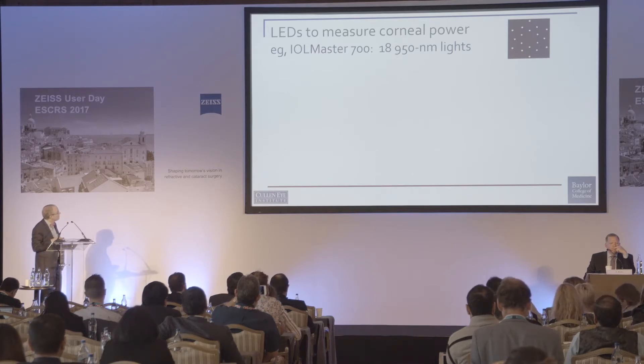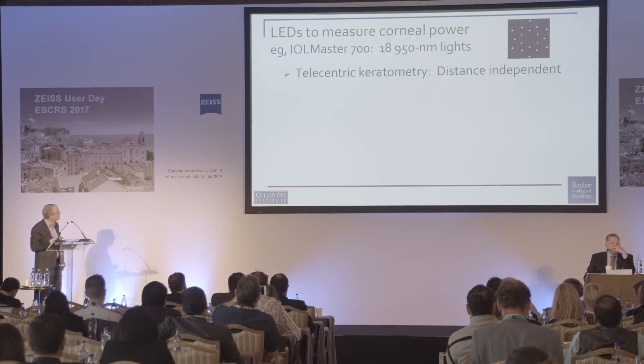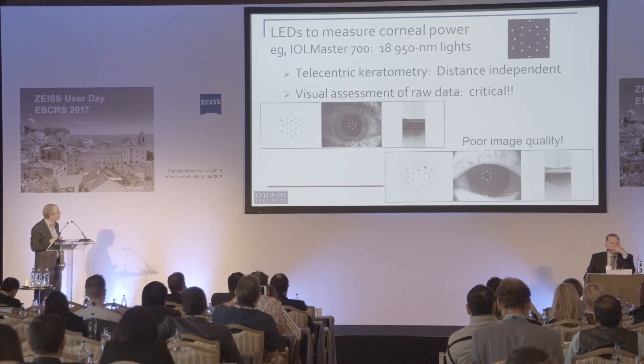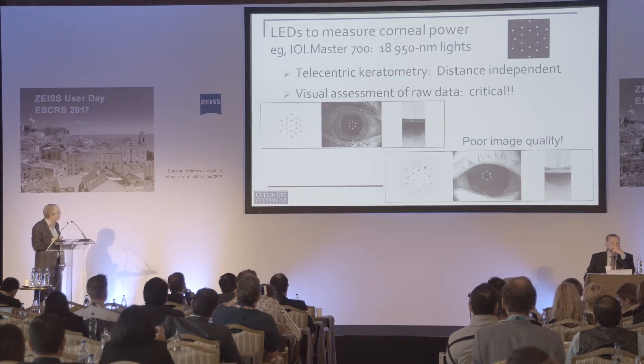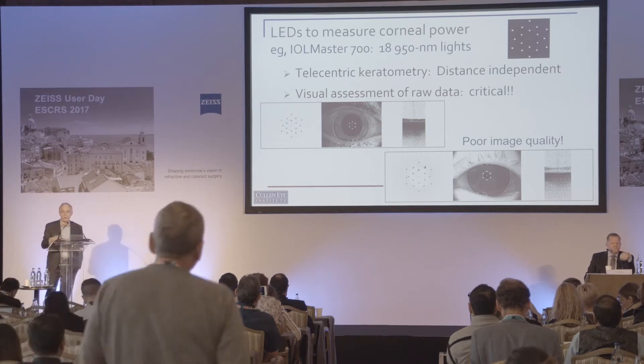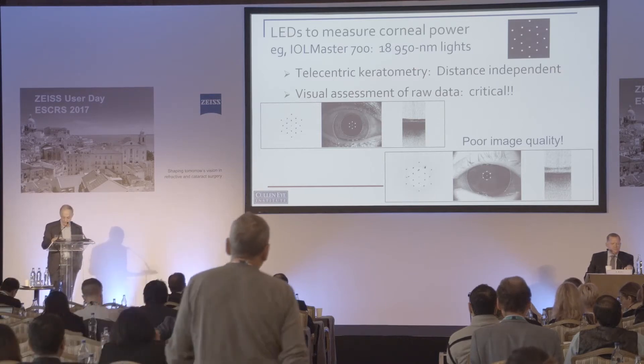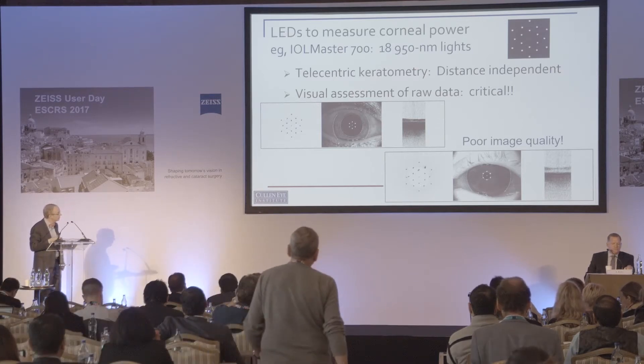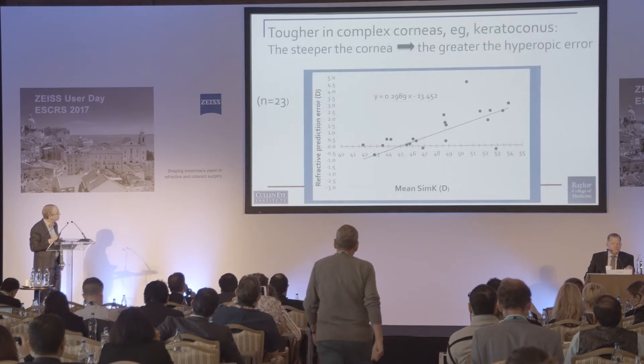The IOL Master 700 has 18 of these 950 nanometer lights, and we've heard about the telecentric keratometry. I'm a big fan of looking at the visual imaging of the reflections of the LEDs — the Mires — and this to me is one of the great qualitative ways that I can judge whether or not I have a good reading on these patients.